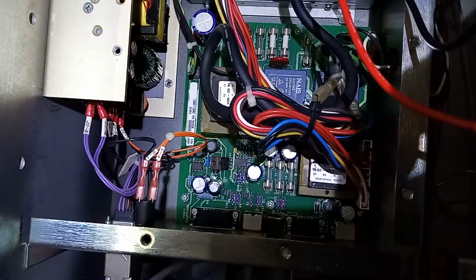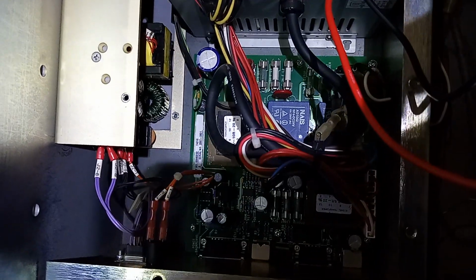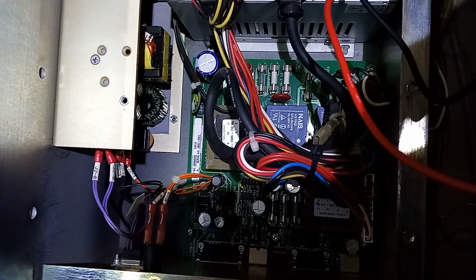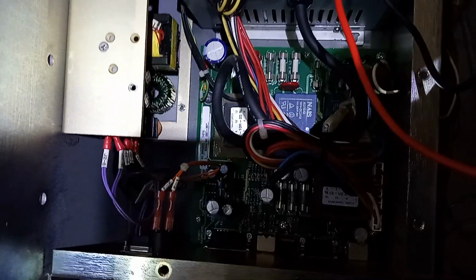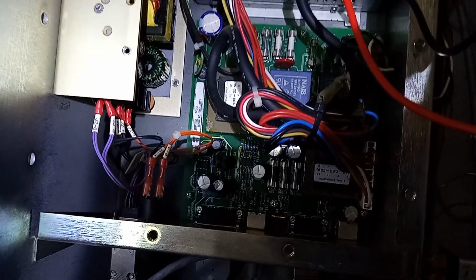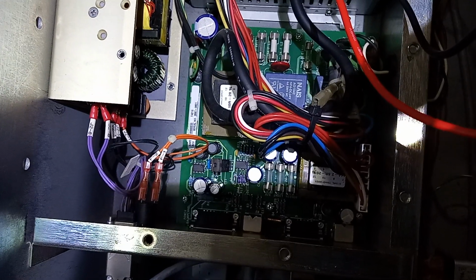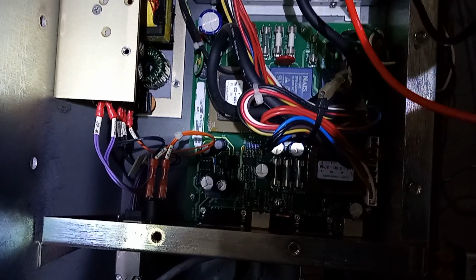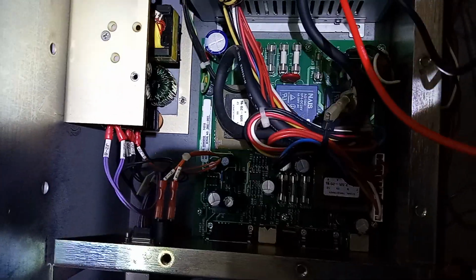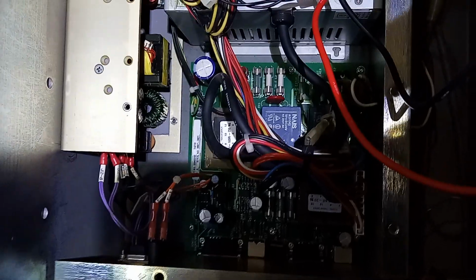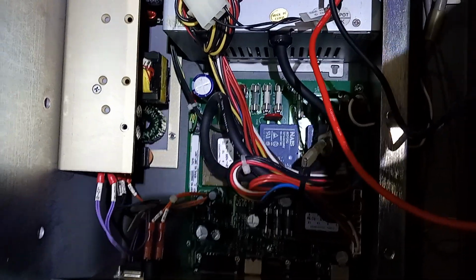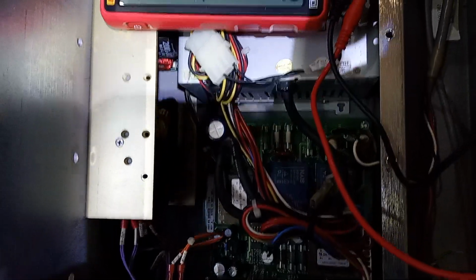That completes the test. I'm testing the power supply voltages on the EMT10T machine. Also, the EMT10T F1 should be similar - all the voltages should be the same, and all the fuses should be okay too. There's a power supply that might vary; I've seen other types of power supplies, but if you have this type, this is the one that we're testing. That's how you test this one here.